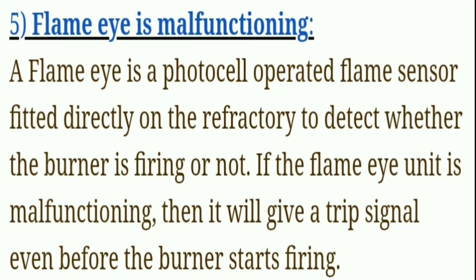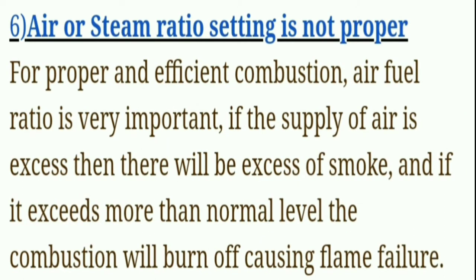Fifth, the flame eye is malfunctioning. A flame eye is a photocell-operated flame sensor fitted directly on the refractory to detect whether the burner is firing or not. If the flame eye unit is malfunctioning, it will give a trip signal even before the burner starts firing.